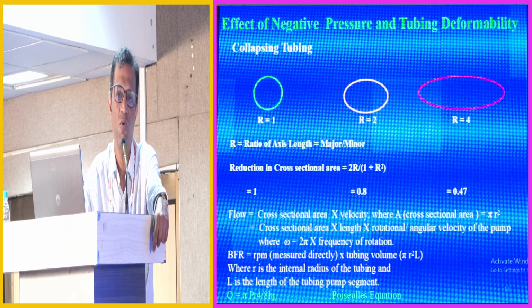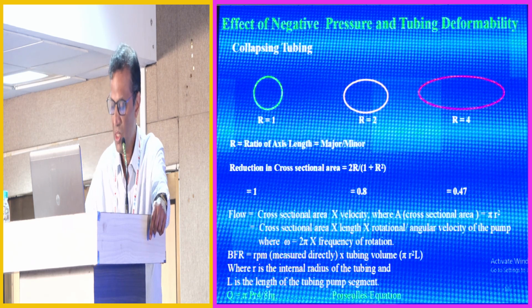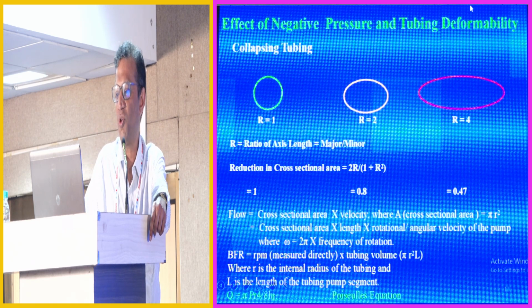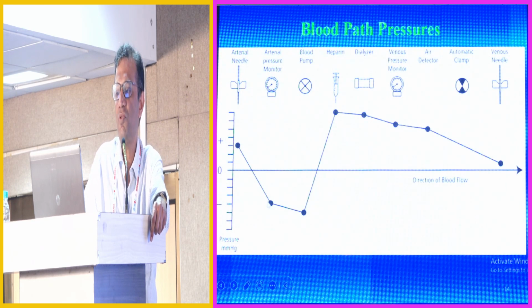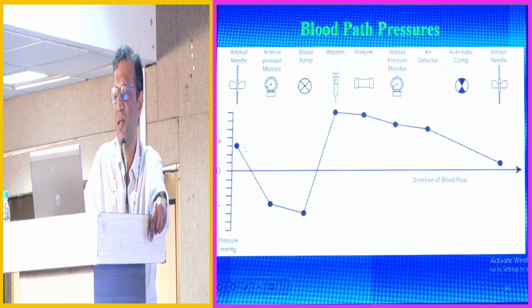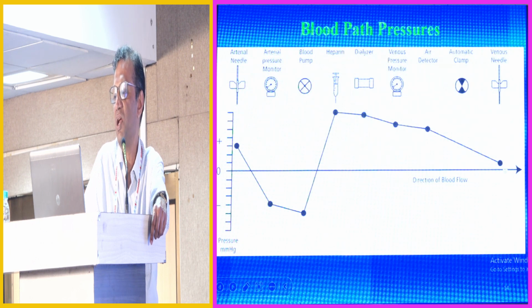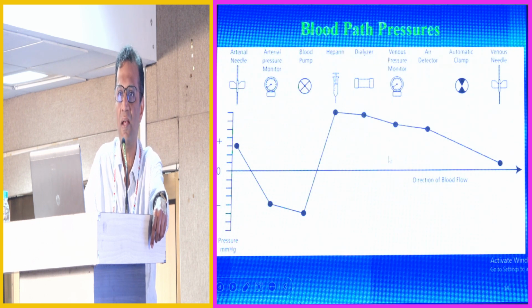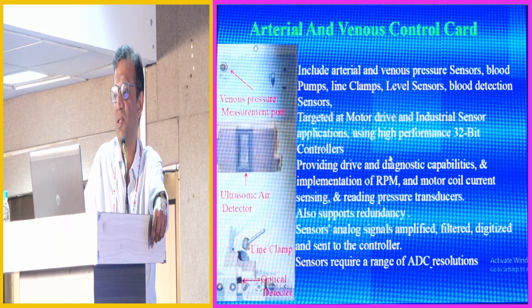And you can see this if you connect your arterial pressure port. This is what happens to the pressures in our blood tubing. The pressure is at its most negative just before the blood pump and at its most positive immediately after the blood pump. So there is an acute transition from a negative pressure, as has been said earlier, to a positive pressure, and then it gradually dips down, being the lowest where the blood enters the venous access.